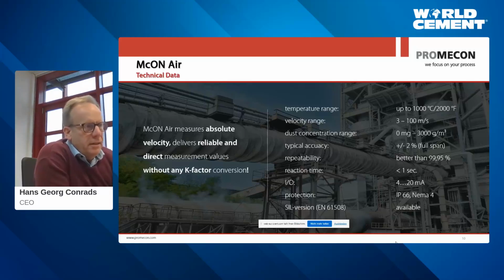Of course, this depends a little bit. If you are mounting our system directly after a bend, of course, you have to analyze how representative our measurement is in that location. But if you look at a long duct, as you can see in the background of this, the nice long tertiary duct, you don't have this issue.